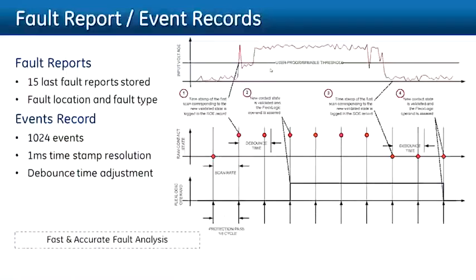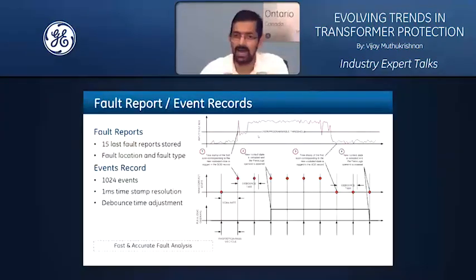The next one is fault report and event records. These two are more driven around faults and any alarms or events happening as seen by the transformer. A fault report can give you a pre- and post-fault snapshot of the data in terms of electrical characteristics. Event records, on a sequential basis, log all the different events triggered as seen by the relay itself. The timestamp resolution of these events can be less than 1 millisecond, as it is in 845.